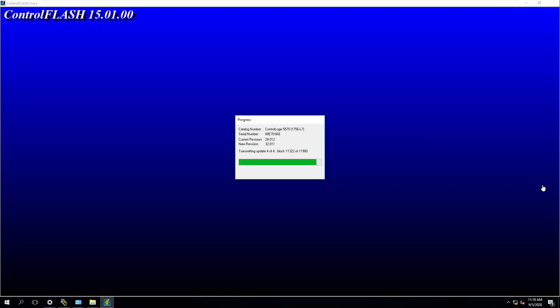So I did want to unpause this real quick to show you the end blocks as it's four blocks that's got to transfer. And then when it gets done, it's going to start polling and reset your processor. So, again, this is the part where it comes back and it makes sure that everything is there and it goes and it cycles the power on the actual processor internally. It sends the request to do that. Now, there are instances too where you definitely need to, you know, you may have to have your processor if they already has a program involved. You may need to put that program inside of, you know, like a program mode or something like that instead of a run mode because, again, it's not going to let you flash. But what I will say too is you need to make sure you have your program backed up before you do that because if you do, you will lose everything that's in this processor. So make sure you know that.